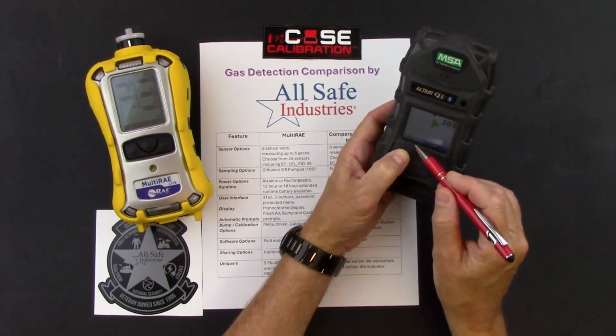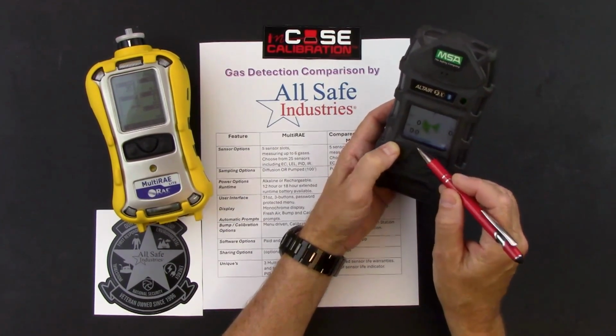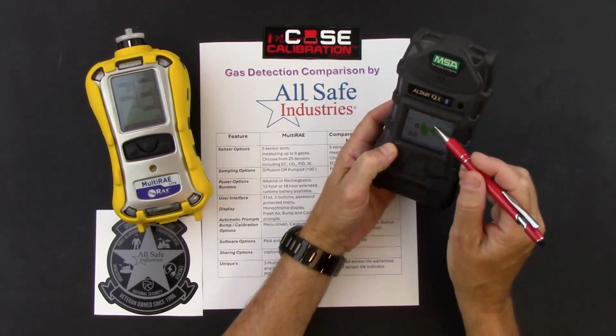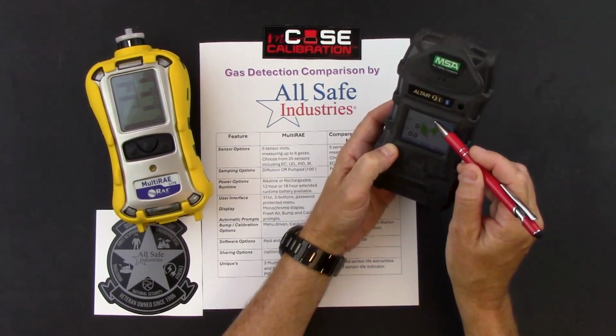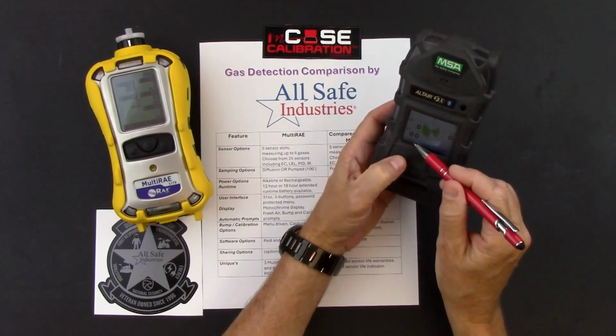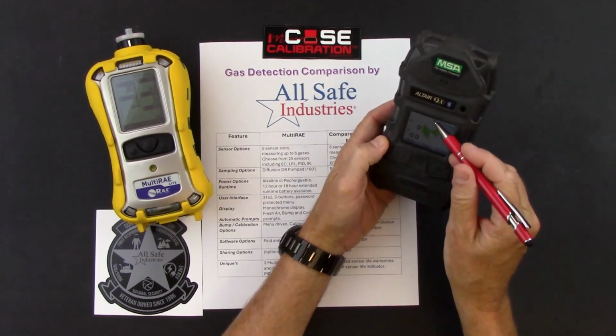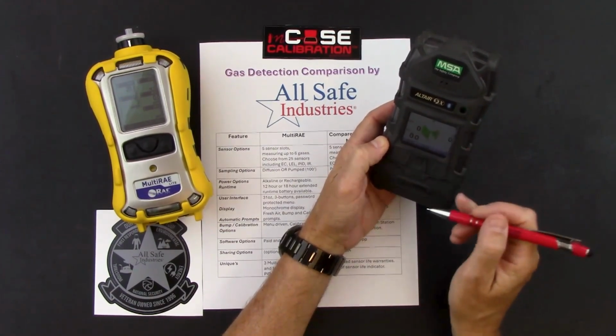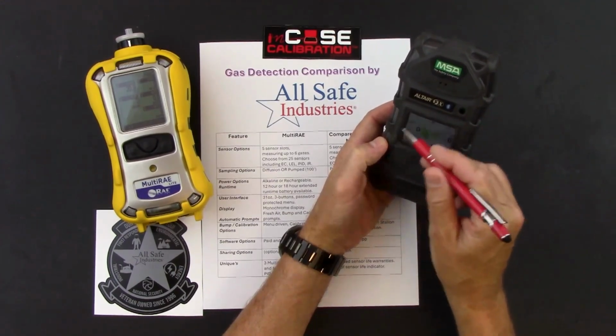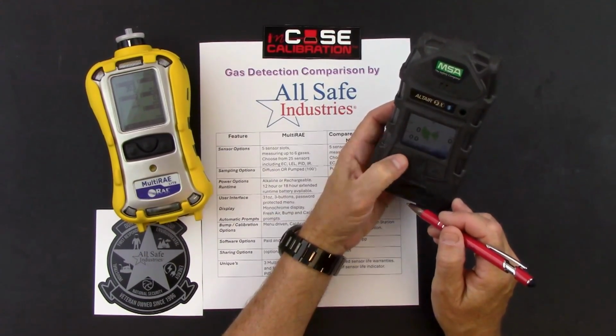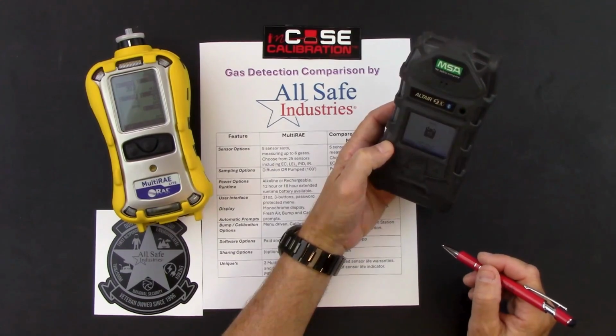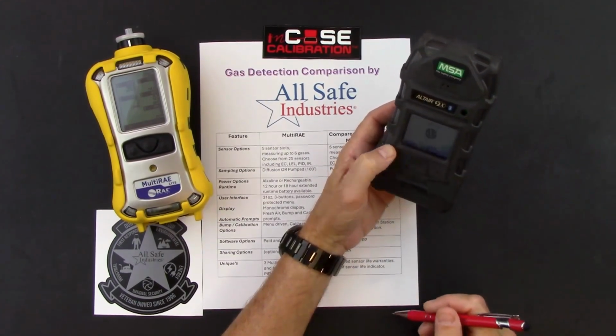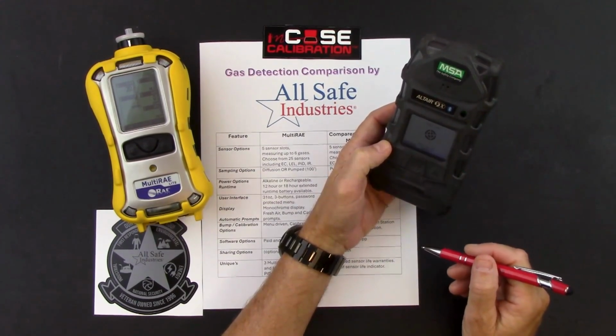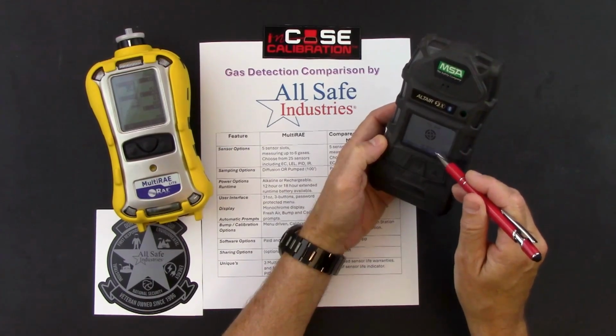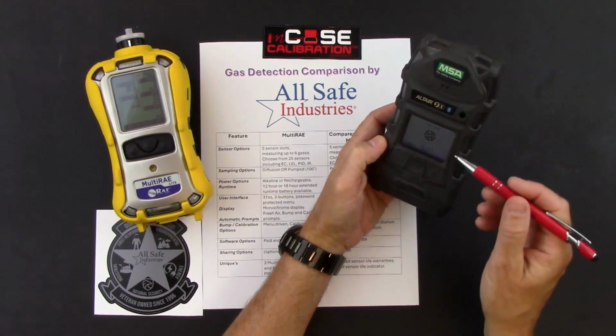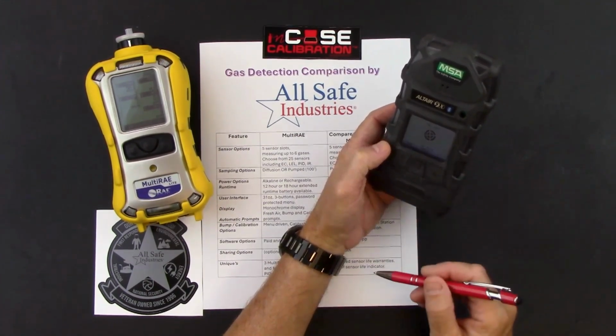You can see that my next menu is going to show me my short-term exposure limits. And so that's here with the icon only showing 15 minutes highlighted. If I hit the button again, these are my time-weighted averages, and you can see the icon up here has changed a little bit to show me that longer calculation. My next screen is my date. My next screen shows me my last calibration date. My next screen is labeled Cal Due and shows me when my calibration will be due again. MSA likes you to calibrate every 60 days.